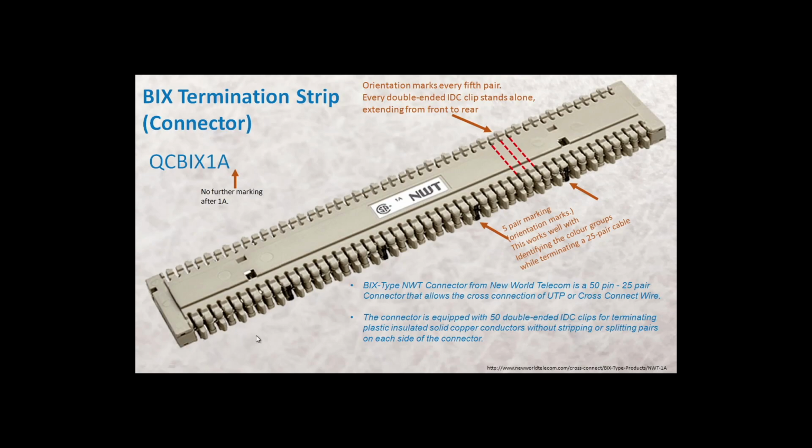So here would be group 1, because once you terminate that and flip it to the back, it's easier to see where's the first group, there's the second group. So here would be the white group, here would be the red group, there's a black, yellow, and violet group, and the colors repeat: blue, orange, green, brown, slate. Blue, orange, green, brown, slate for every color group. Okay, so these are just orientation marks.